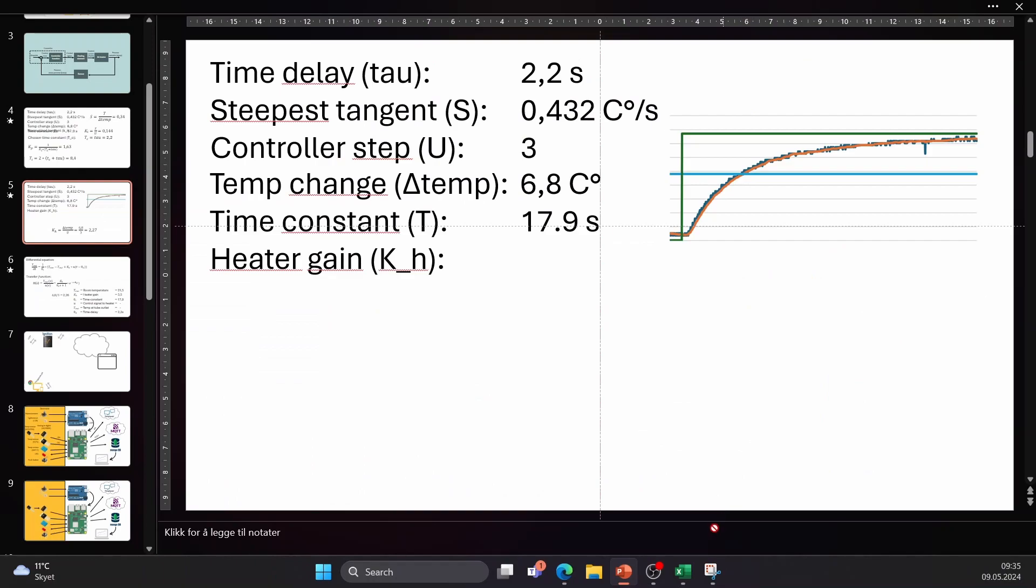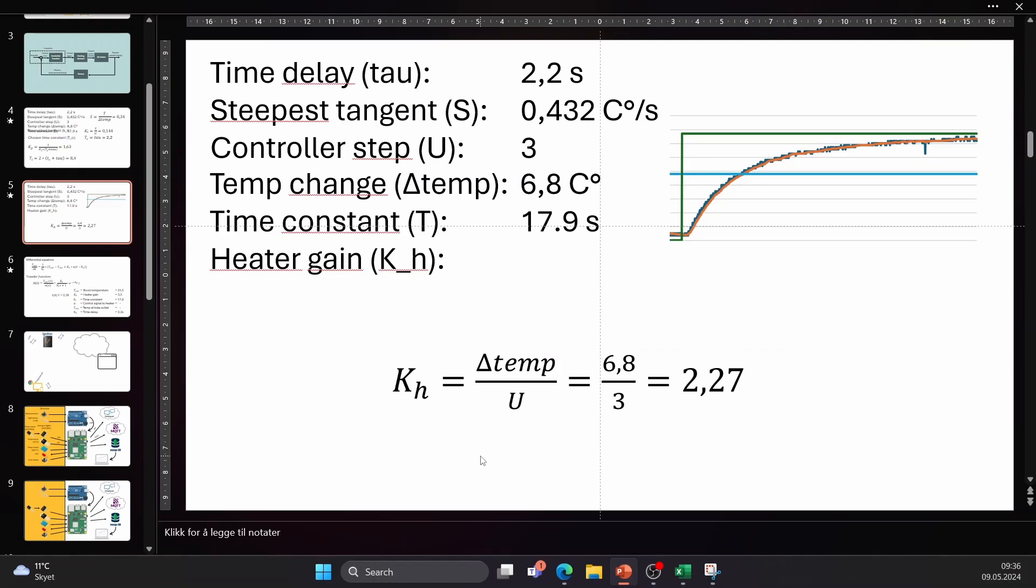Since we have done a step response test on the system we also have enough information to create a mathematical model of the system that we can use to simulate the system. The only value we are missing is the heater gain which is the internal gain in the process from the input to the output in a steady state. To calculate that we need to divide the total change in the temperature by the step change we did. And the result is a gain of 2.27.